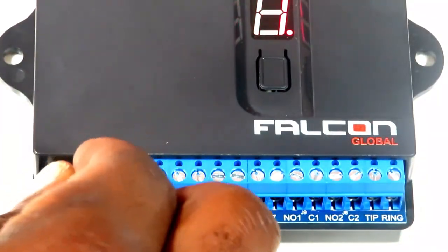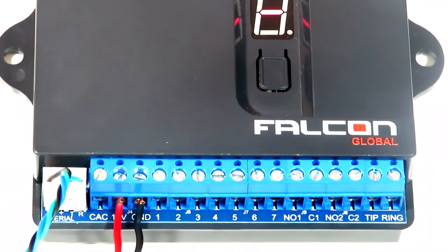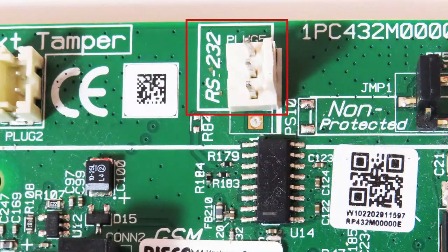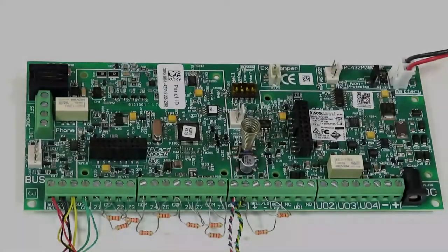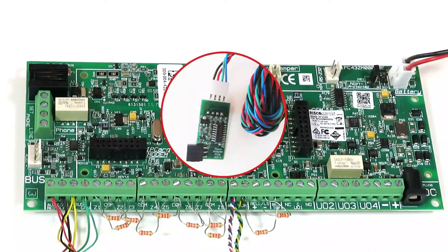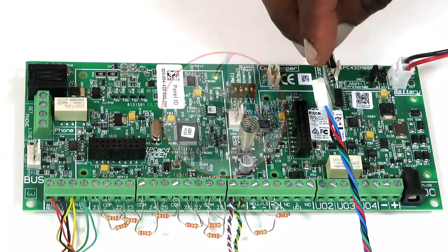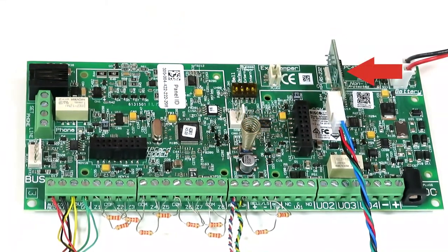Connect the Falcon to the Risco LightSYS 2 through the serial port RS-232, using the serial cable and adapter marked Risco provided. Note that the adapter must be connected to the panel serial port, with the adapter board facing right and the blue wire on top.